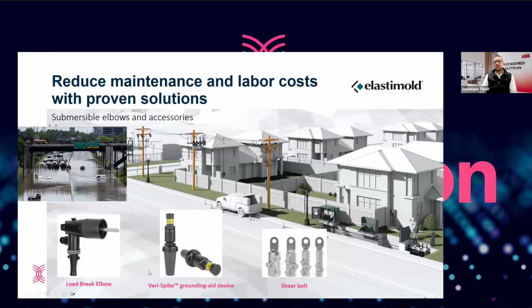There's also attachments like the Veri-Spike ground aid. That's a component implemented into a circuit that lets you spike a line—cutting it to confirm if there's power inside the copper contact without damaging the cable itself. The former method was to spike the cable directly, cutting it off and having to shorten it, add cable, or splice it, costing a lot of man hours, time, and investment. With this spiking aid, once you cut through it and confirm the line is dead, it's easy and relatively cheap to replace.